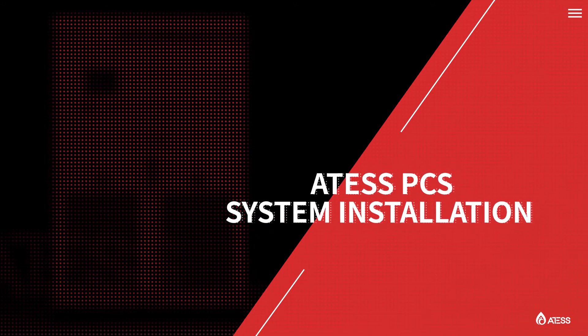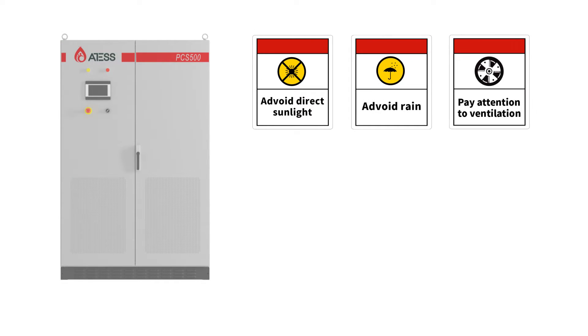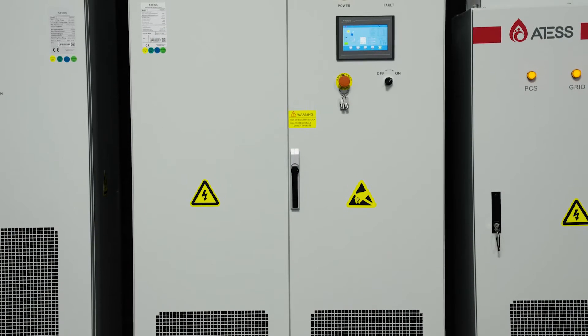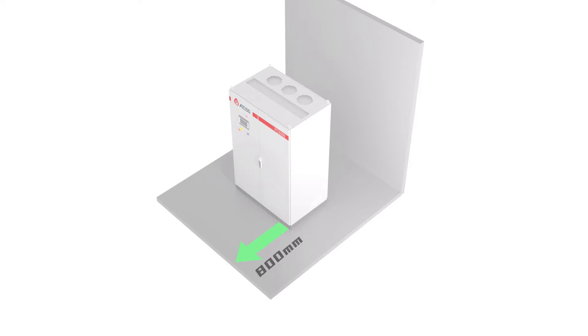Welcome to the ATESS PCS System Installation video. The equipment should be installed indoors to avoid direct sunlight or rain. Keep ventilation clean at all times and stay away from residential areas. It is recommended to install in the power distribution room. Equipment should be installed on flat, solid, firm ground with flame-retardant material surface or channel steel structure. At least 800mm clearance must be kept around the equipment to ensure cool operation.